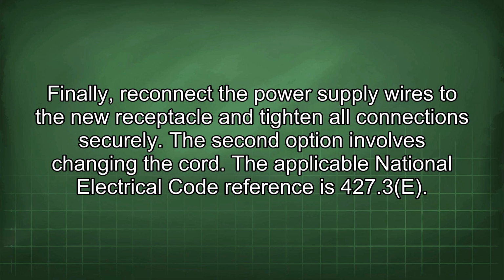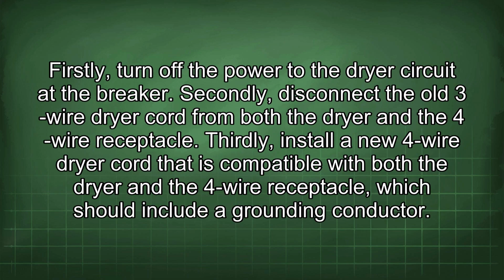The second option involves changing the cord. The applicable National Electrical Code reference is 427.3. Firstly, turn off the power to the dryer circuit at the breaker. Secondly, disconnect the old 3-wire dryer cord from both the dryer and the 4-wire receptacle.